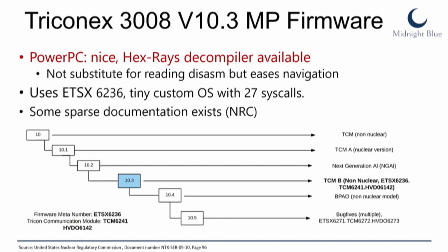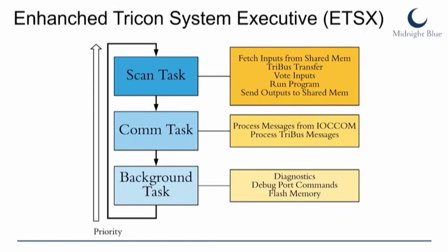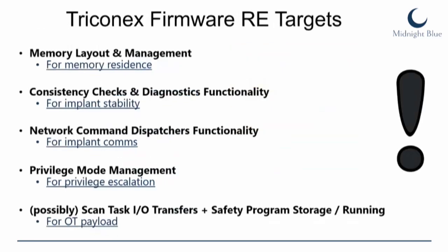It uses a custom operating system with 27 system calls, and some sparse documentation exists. Basically, this is what the operating system looks like. You have a scan task, a communications task, and a background task, and we're really only interested in the scan task, which fetches inputs from shared memory, where all the analog and digital I/O gets put. Then we do a TriBus transfer for the voting on consistency, and then we run the actual control logic, and then we send the outputs again to the shared memory.